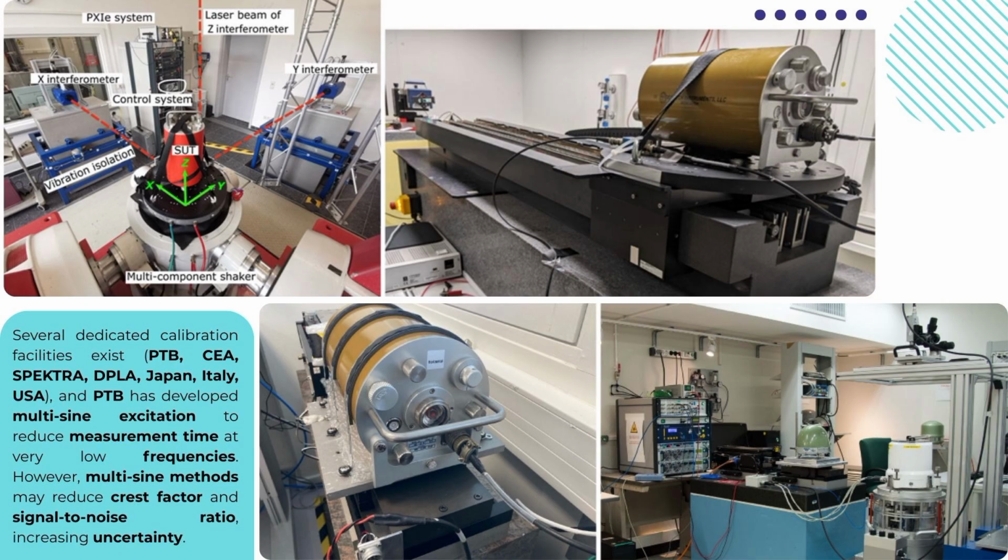As you can see on the screen, several dedicated calibration facilities exist, such as PTB, CEA, Spectra, DPLA, Japan, Italy, and USA. And PTB has developed multi-sine excitation to reduce measurement time at very low frequencies. However, multi-sine methods may reduce crest factor and signal-to-noise ratio, increasing uncertainty.